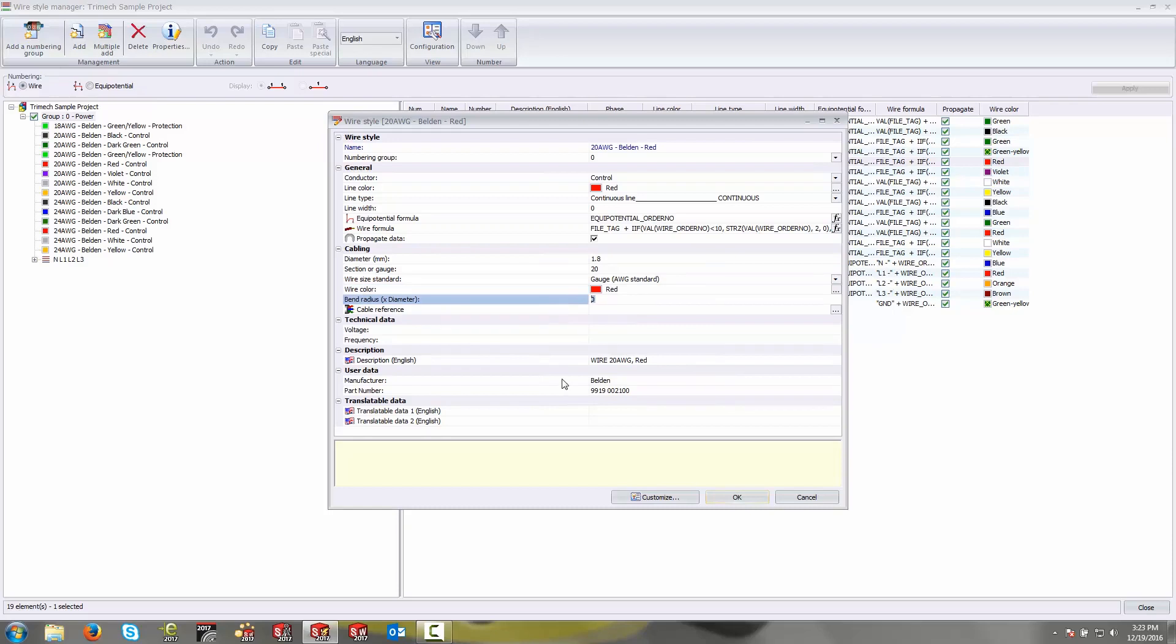Bend radius relates to the minimum bend radius of this particular wire. This has specific functions in SolidWorks Electrical 3D. When this is routed, this value here will be taken into account when the software is routing this wire, and will flag you if this value is exceeded when you're taking tight bends around corners.